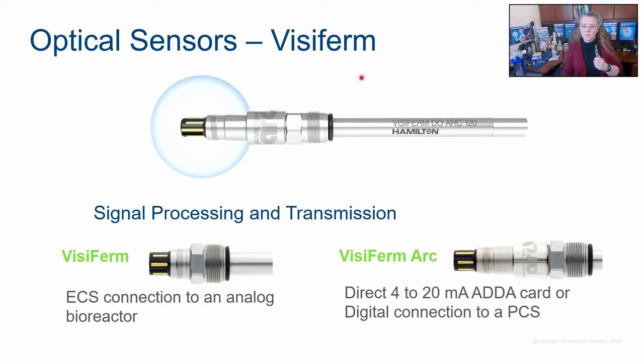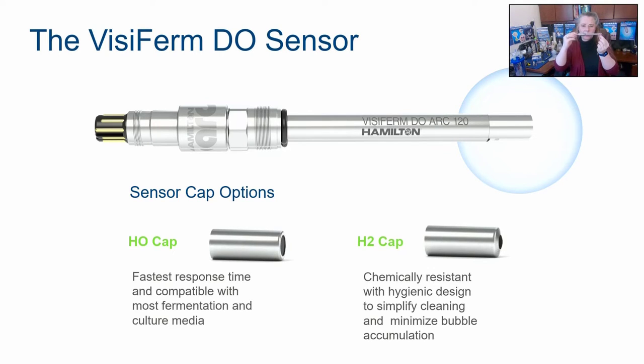And then we have our arc family like this that can give you a 4 to 20 signal or a digital connection to a PCS or a controller system. When I say digital, and we'll talk about this a little bit later, but any sort of digital platform. New bioreactors require digital signals, Modbus, OPC, things like that. The anatomy of these sensors is pretty easy. We have the sensor, and there are caps. The whole sensor. The types of caps you have, for Hamilton, we have two different caps.